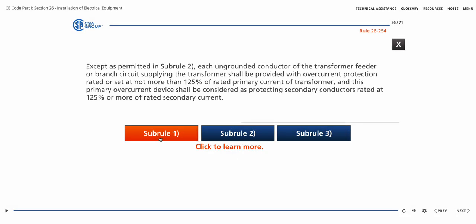Subrule 1. Except as permitted in Subrule 2, each ungrounded conductor of the transformer feeder or branch circuit supplying the transformer shall be provided with overcurrent protection rated or set at not more than 125% of rated primary current of the transformer, and this primary overcurrent device shall be considered as protecting secondary conductors rated at 125% or more of rated secondary current.